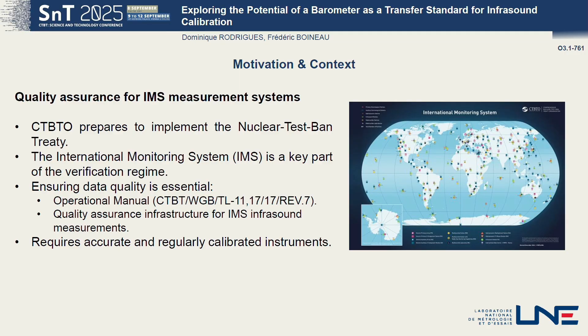So, the infrasound measurements within the IMS must be traceable to the international system of units, and this metrological traceability means different needs at different levels. On the top, we will find the first realization of the unit, the primary reference standard, which is usually established by a national metrology institute. And at lower levels, we will find the accredited labs and expert labs, which require working or traveling standards in order to perform secondary calibration of sensors, usually by comparison against such a working standard.